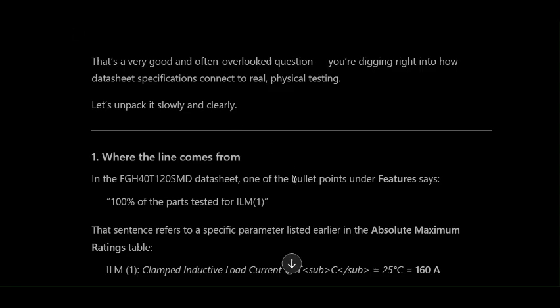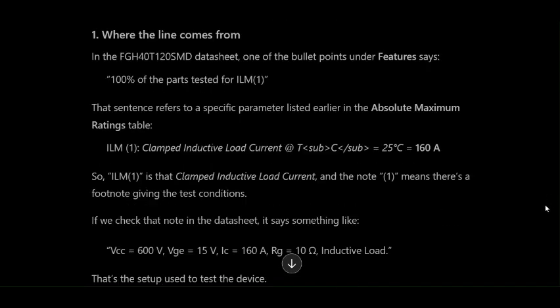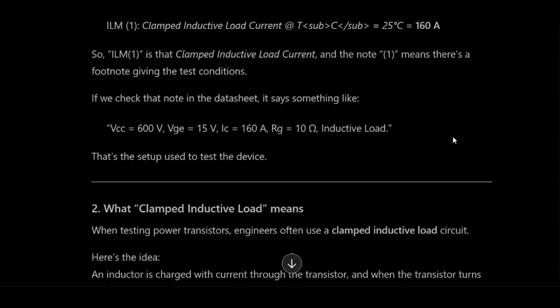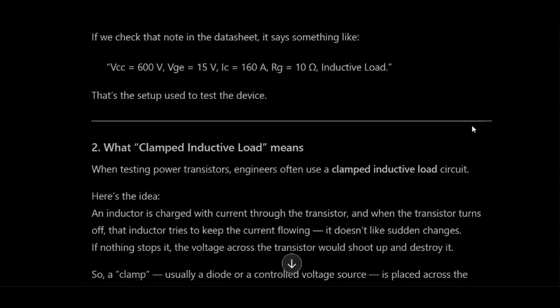First, where the line comes from. In the FGH40T120SMD datasheet, one of the bullet points under features says '100% of the parts tested for ILM1.' That refers to a parameter in the absolute maximum ratings table: 'ILM1, clamped inductive load current at TC equals 25 degrees Celsius, equal 160A.' The note 1 gives the test conditions: 'VCC equals 600 volts, VGE equals 15 volts, IC equals 160A, RG equals 10 ohms, inductive load.' That's the setup used to test the device.